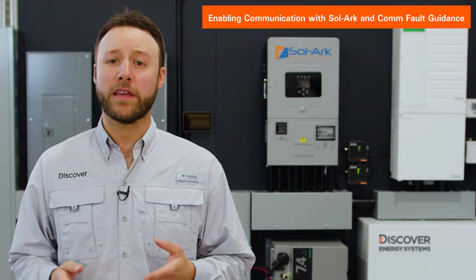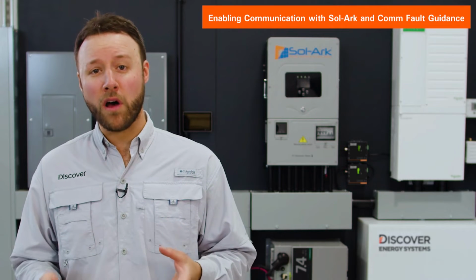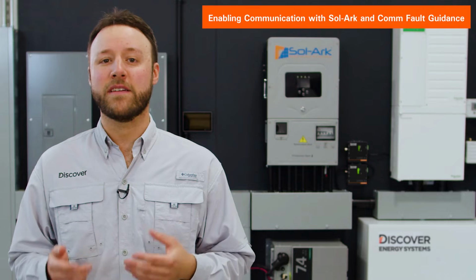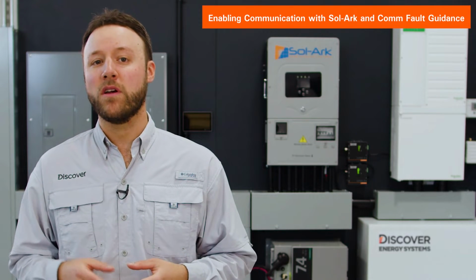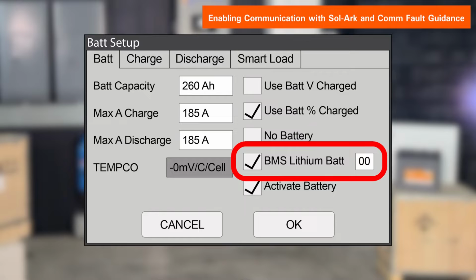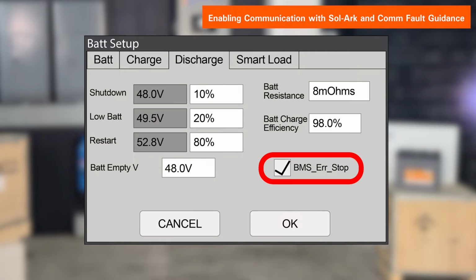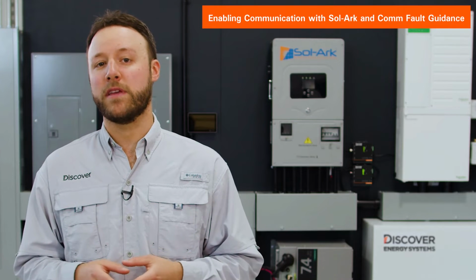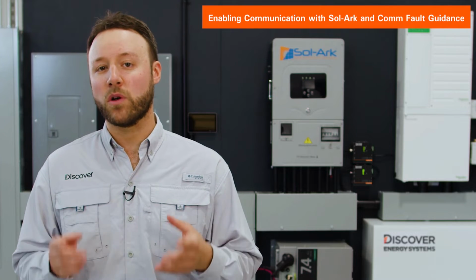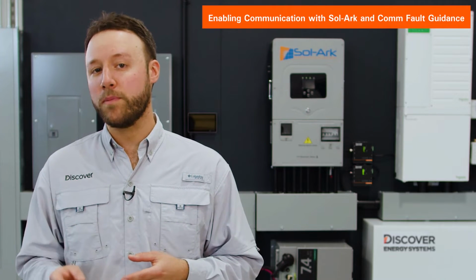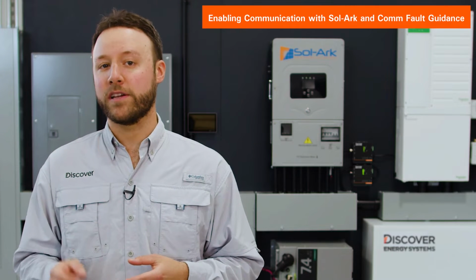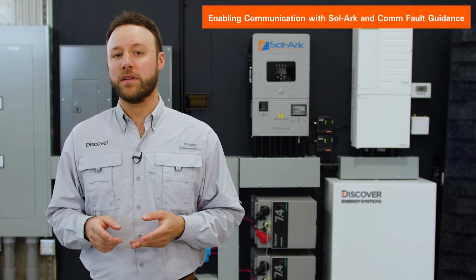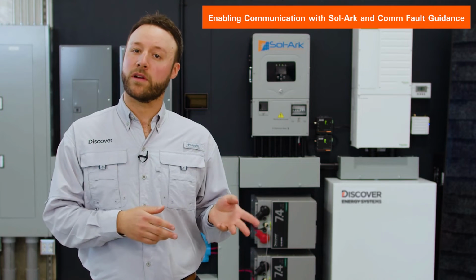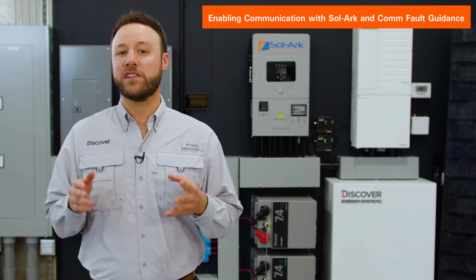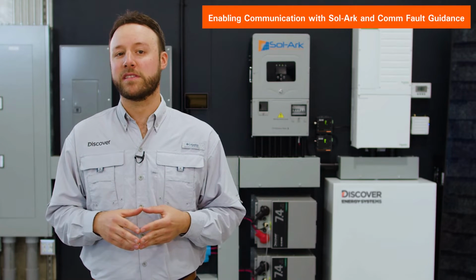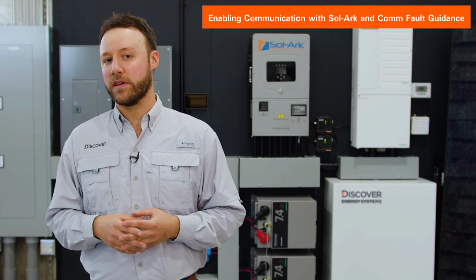Be aware that if communication between the LYNK II and the inverter is lost for more than 10 seconds, the inverter will safely stop operation only if the inverter's BMS Lithium BAT and BMS error stop parameters are both enabled. If closed-loop communication can't be reestablished, the Sol-Ark inverter must be changed to an open-loop configuration to resume operation. As a precautionary measure, we recommend to first program the Sol-Ark inverter with the correct voltage-based open-loop parameters before setting up the system to function in a closed-loop configuration.